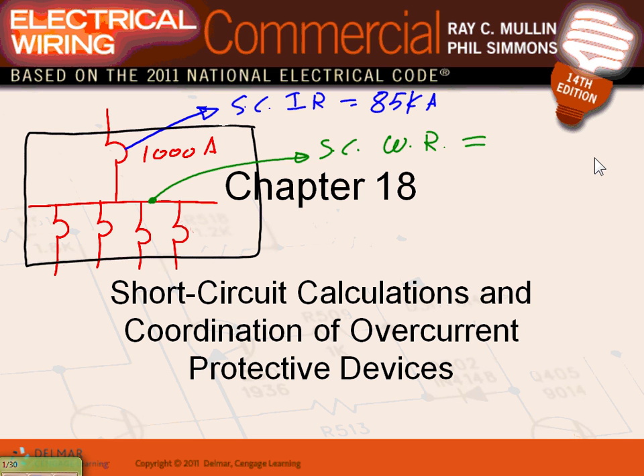Usually it's the same, 85,000 amp. So this switchgear can handle a withstand rating up to 85,000, meaning it's intact. If you go higher than that, the switchgear itself is going to blow. If you go higher than that, the contacts of the circuit breaker might weld together. They don't open, they weld.